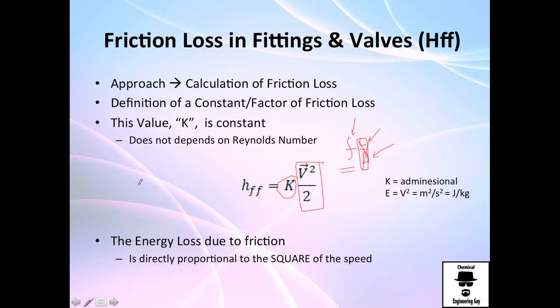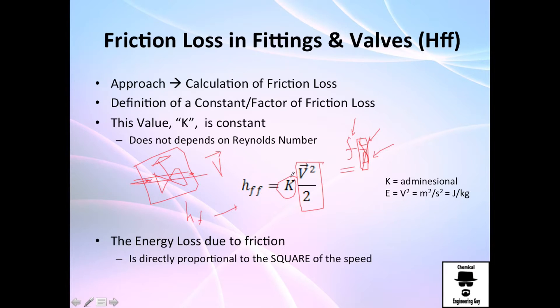Imagine you have a pipe with a valve and want to calculate the friction loss. They apply the mechanical energy equation between the inlet and outlet of the valve, measure all the energy lost, and check how that energy loss depends on velocity. They get this K constant. The interesting part is that the value of K does not depend on the Reynolds number — K is constant regardless of flow speed.